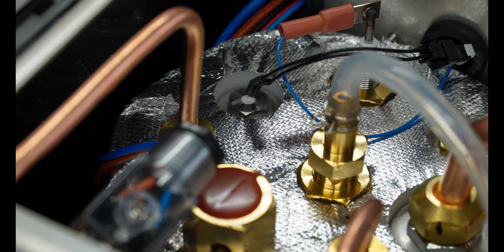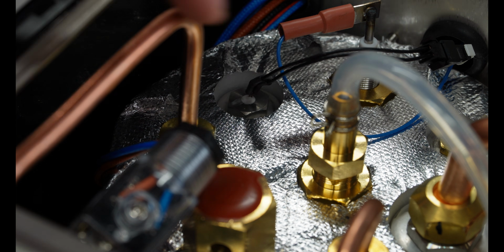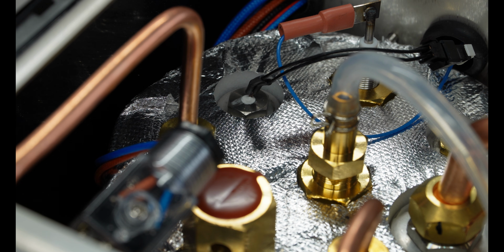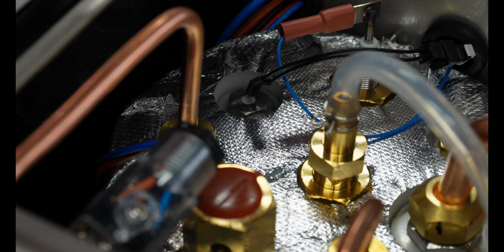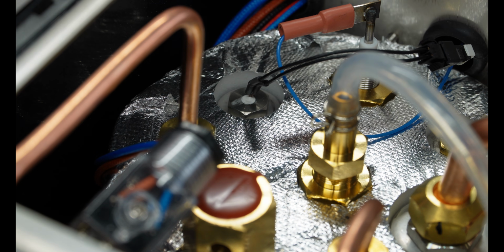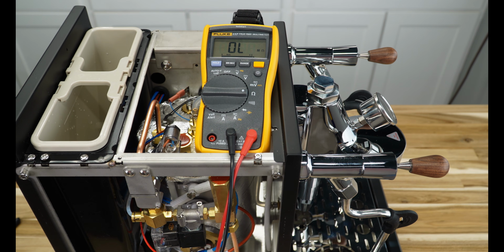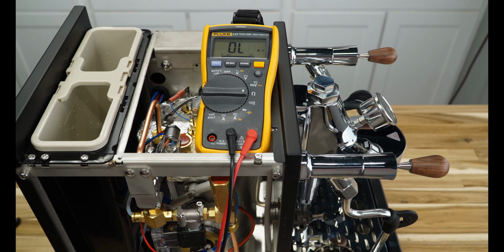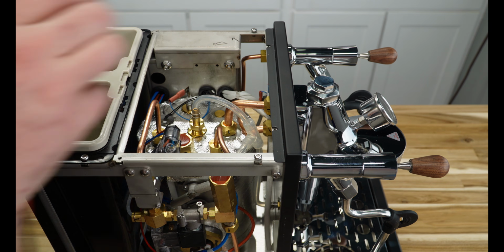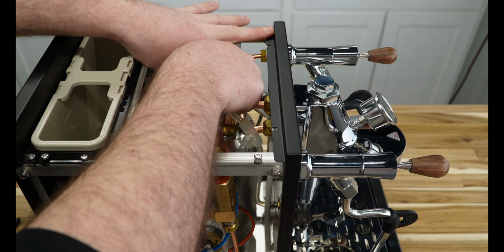So sometimes this wiring will become damaged and your machine, for whatever reason, won't heat up because it's not getting a signal. Now with the modern machines, it's going to tell you that something's wrong. It's going to give you an error message, but we do have a way of testing it just to see if this is what our issue is. So again, we're going to go to our voltage meter and we're going to put it back on the ohms reading and just very gently unconnect these wires.